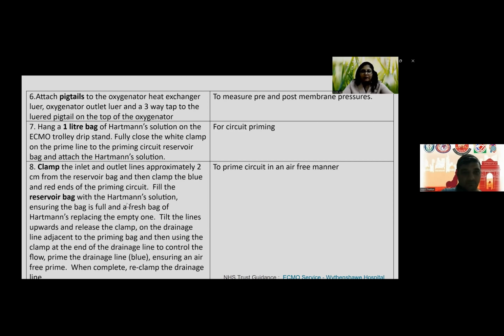You fill the reservoir bag with the Hartmann solution, ensuring that the bag is full, and a fresh bag of Hartmann's replacing the empty one. Tilt the lines upwards and release the clamp on the drainage line adjacent to the priming bag, and then use the clamp at the end of the drainage line to control the flow. Then you prime the drainage line, that is the blue line, ensuring an air-free prime. When complete, you reclamp the drainage line. So all this is done to prime the circuit in an air-free manner.